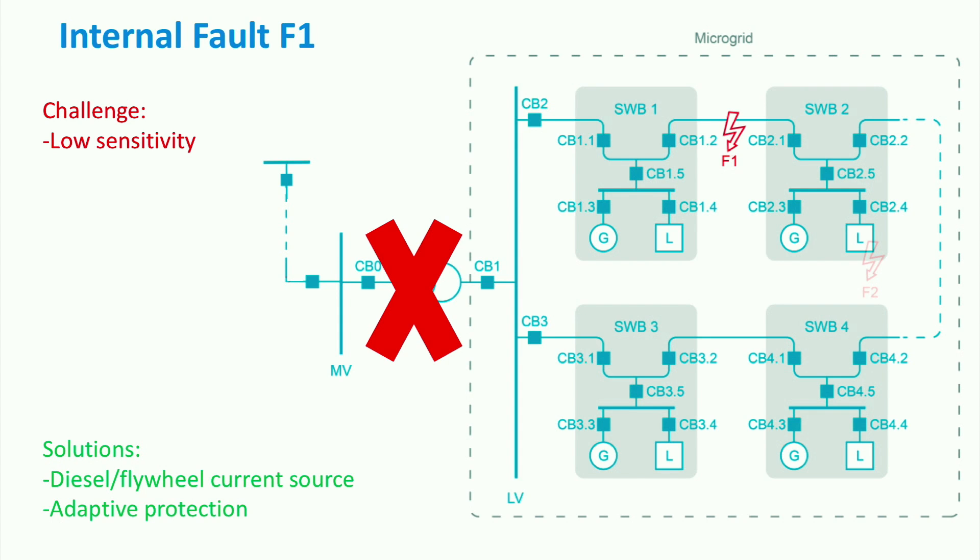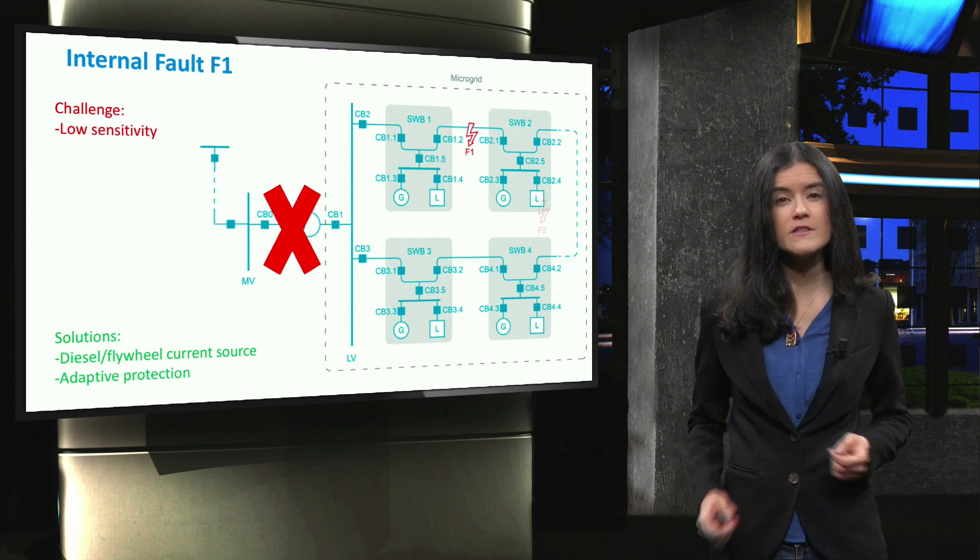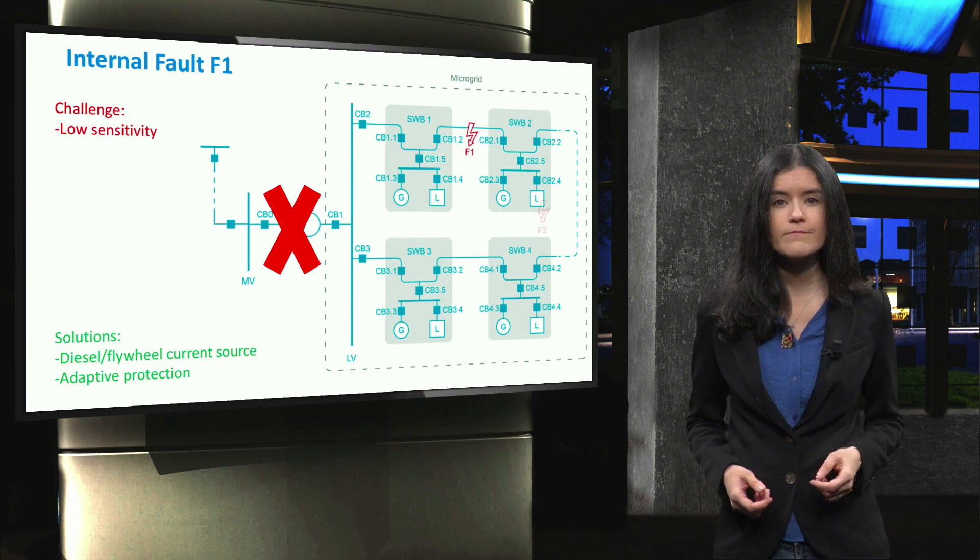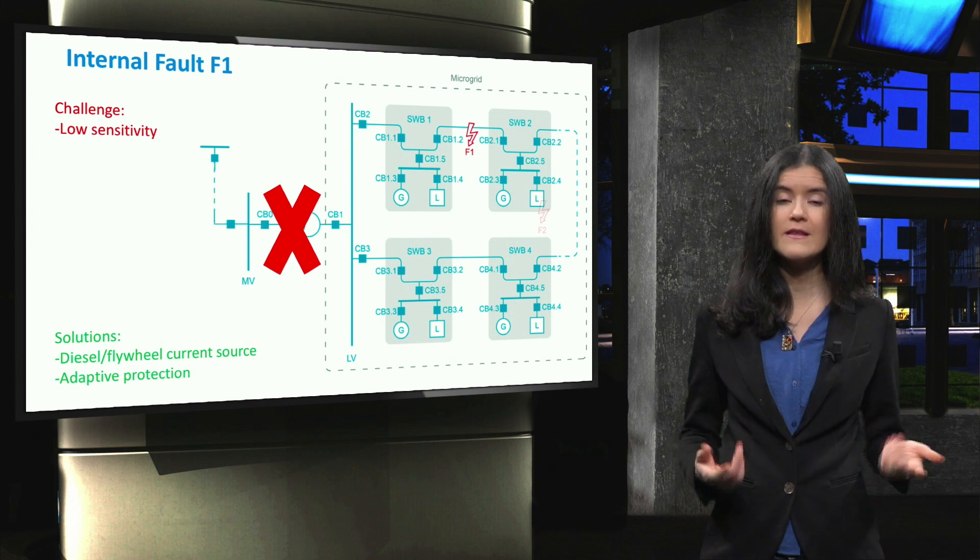The second solution is to implement an adaptive microgrid protection, where the microgrid control system continuously analyzes the structure of the network and actively adjusts the settings of the overcurrent relays in such a way that the protection scheme properly works for different types of system operation and location of faults. We will elaborate more on adaptive protection in some examples in the next videos.